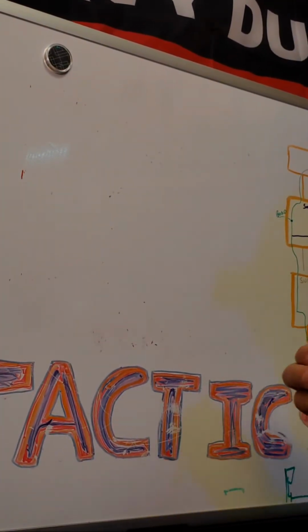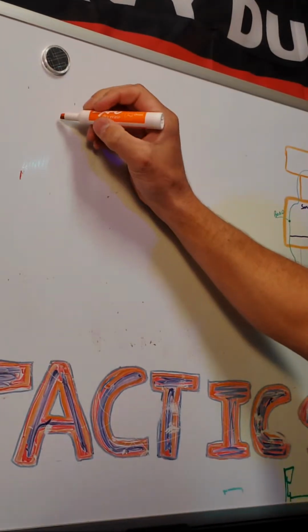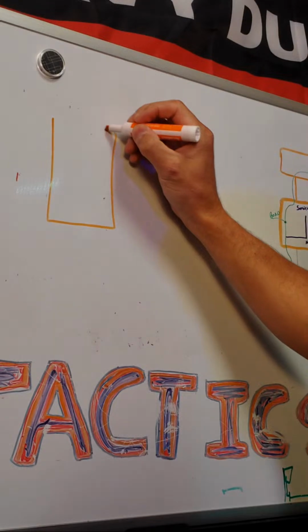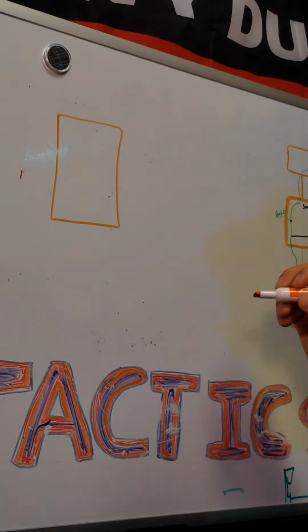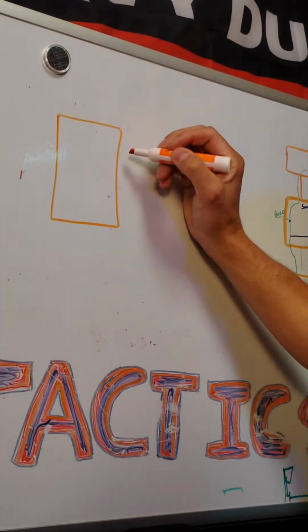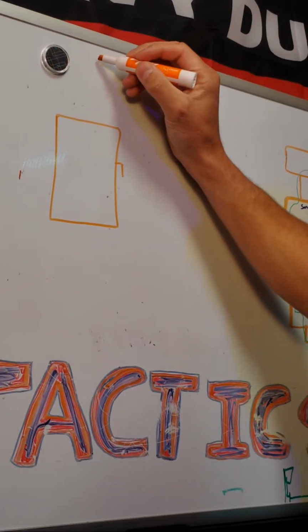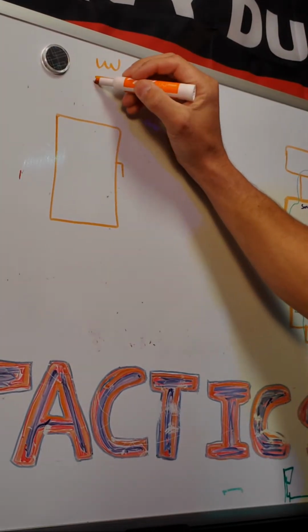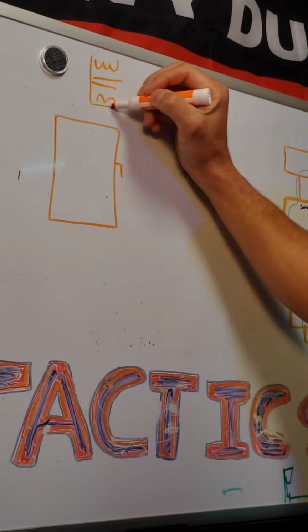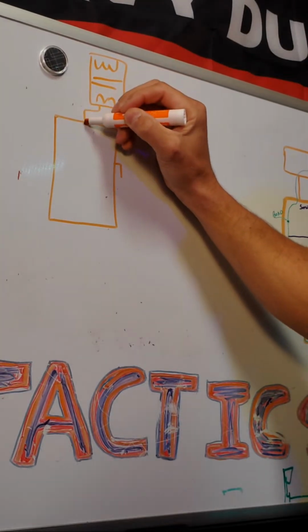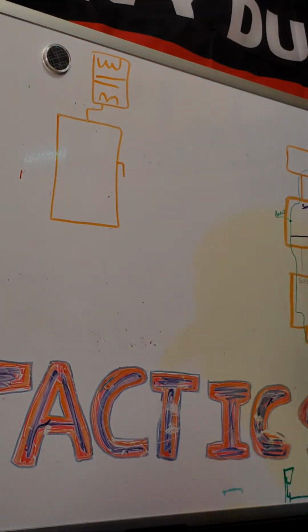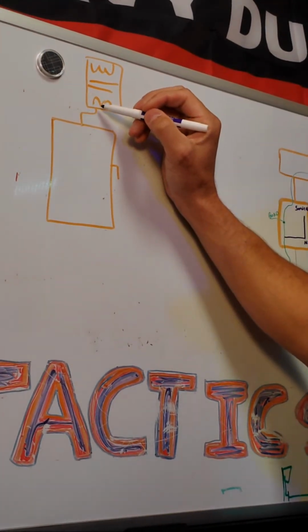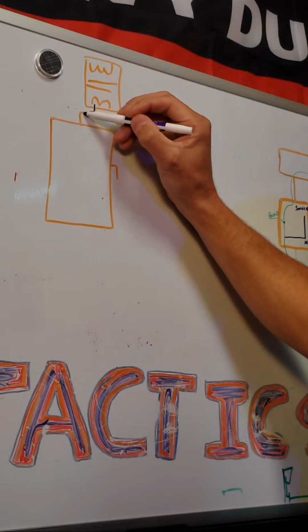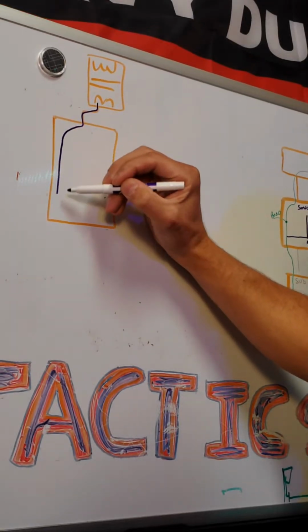When we're talking about a parallel path, if we have a piece of equipment here and it's service equipment and it's coming from a transformer, utility, whatever, and it goes into the top, okay? You have the neutral from the utility. It comes down and it hits the neutral bar.